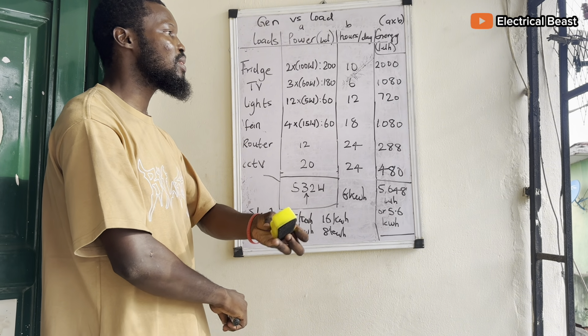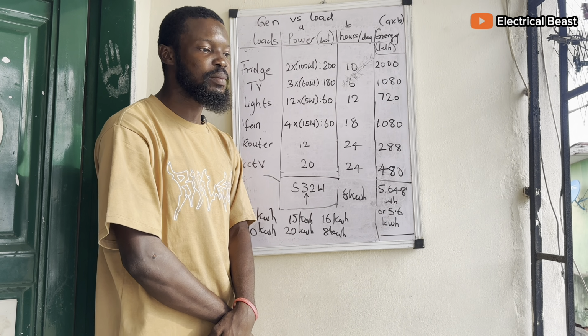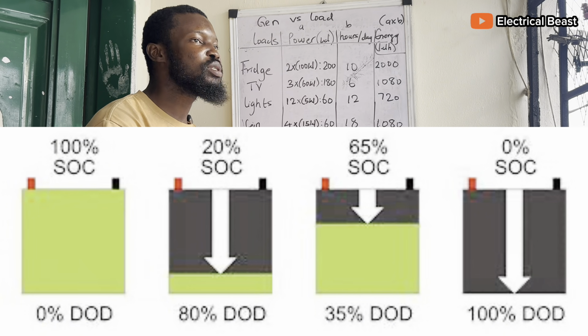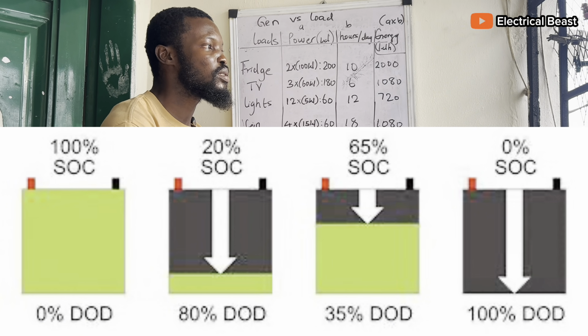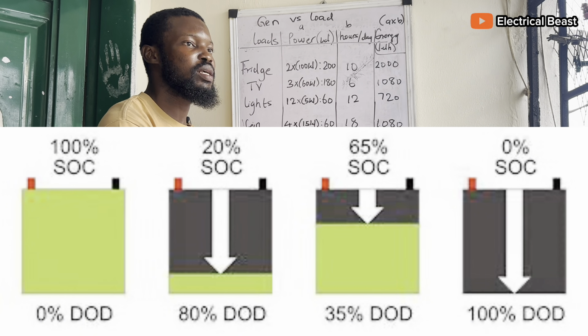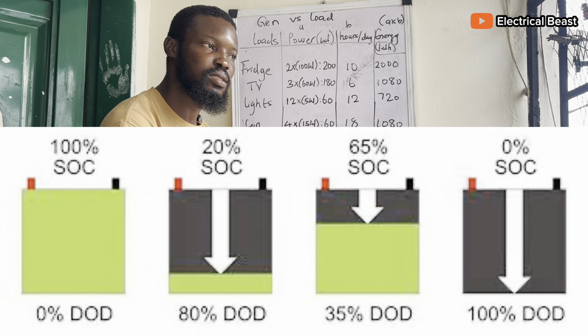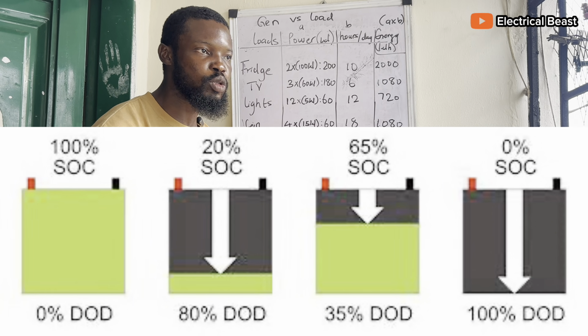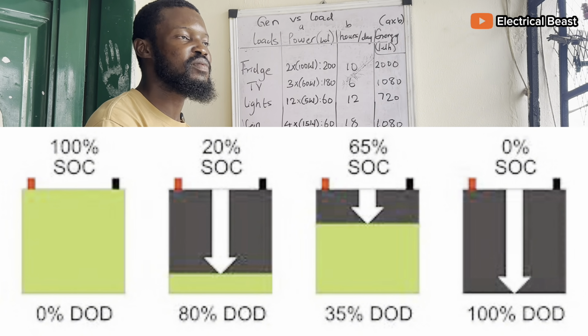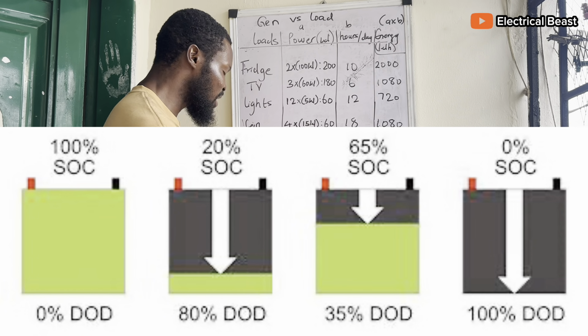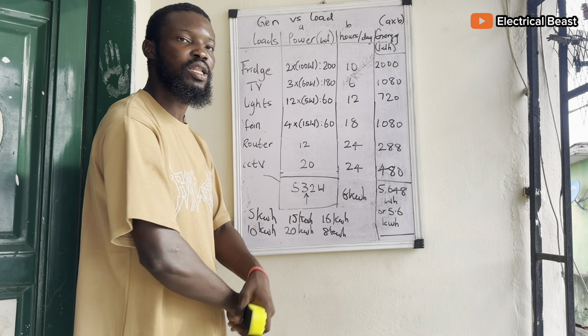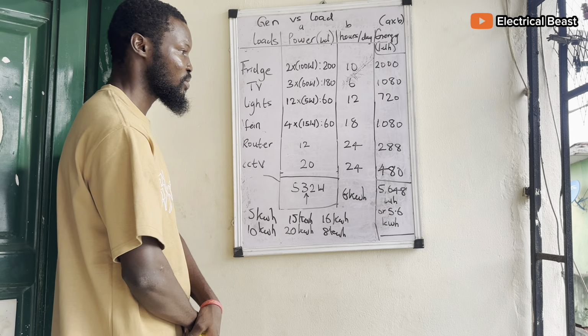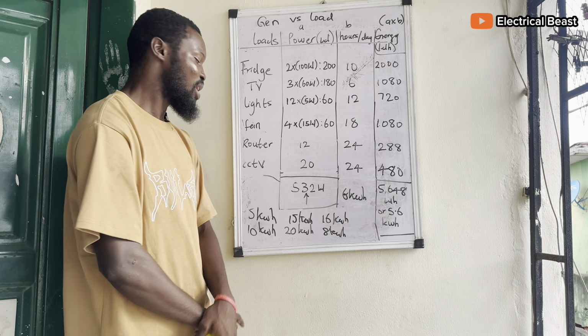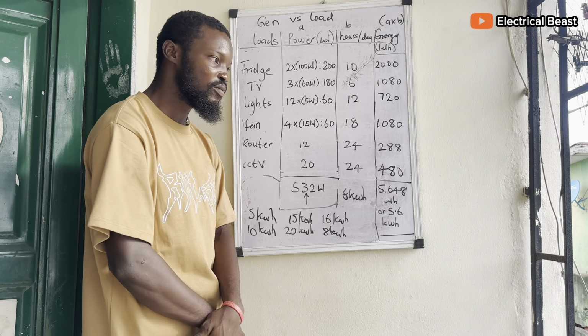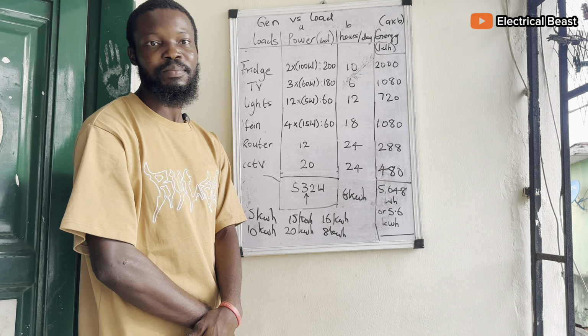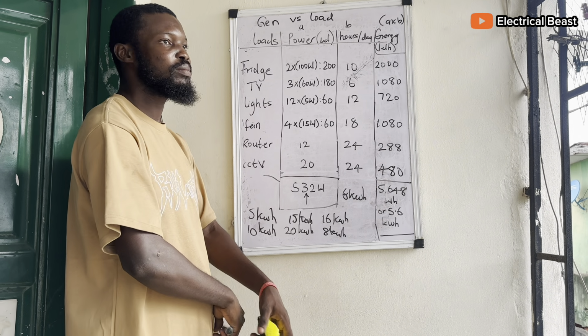Now, there's one thing about lithium batteries you need to know. Lithium batteries, they have depth of discharge. You need to put that into consideration when sizing for solar systems. Now, most lithium batteries, their depth of discharge is about 80%. There are some brands, some good brands that have 90% depth of discharge. That means you have 10 kilowatts, but they will not allow you to use all the 10 kilowatts. They will only give you 8 kilowatts. Some will give you 9 kilowatts. So if you have 10 kilowatts and there's 80% depth of discharge on that battery for that particular brand, it means you can only use 8 kilowatts from that battery.